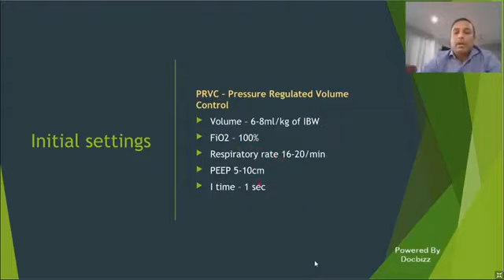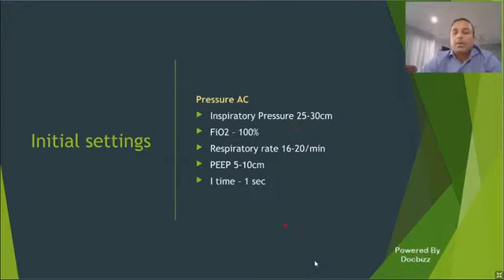Now the pressure control mode, this is pretty straightforward. Again, we put in a fixed pressure. The reason why we choose 25 to 30 is again because of the ARDSNet protocol. We try to keep airway pressures less than 30, but we want to keep the highest close to the point of 30. That way we have the high driving pressures, and the rest of the settings remain the same. Now here again, we are fixing the pressure, but the volume is not fixed, and volume can change with every breath based on the lung compliance.